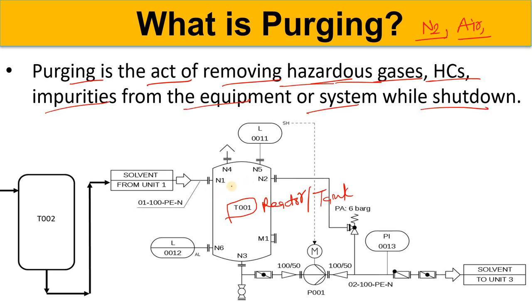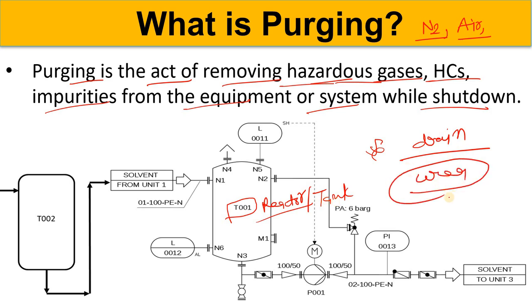If we are doing this with steam, you will simply drain the condensate until the hazardous gases are eliminated. Let's suppose there is urea or ammonia present. When you go closer to the drain and the steam or condensate is going out, you check: if ammonia is no longer coming from the drain, it means the purging has been completed.